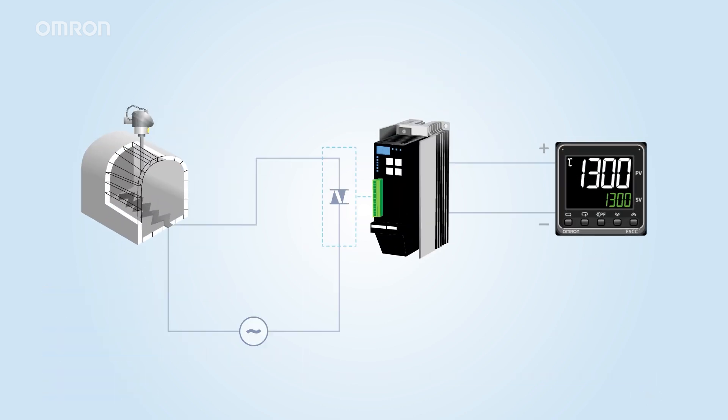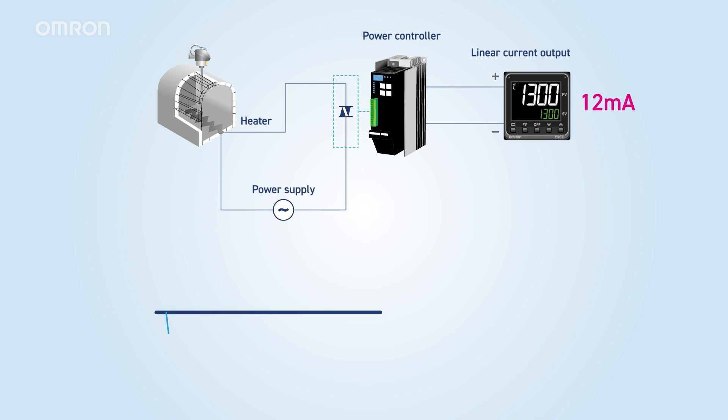When using a power controllers, a temperature controller with a linear current output type is used. The temperature controller continuously outputs a current of 4-20 milliamps to the power controller, which adjusts the on-time of the heater based on the current value.